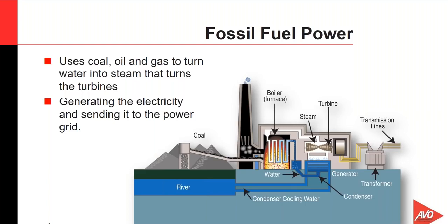Okay. Fossil fuel power is the next one online here. With a fossil fuel plant, much like a nuclear type station, water is turned into steam that is heated from the pulverization and burning of coal, which in turn drives turbine generators to produce electricity. Steam typically reaches temperatures of up to 1,000 degrees with pressures up to 3,500 psi being piped into that big turbine, spinning them giant blades of the shaft.